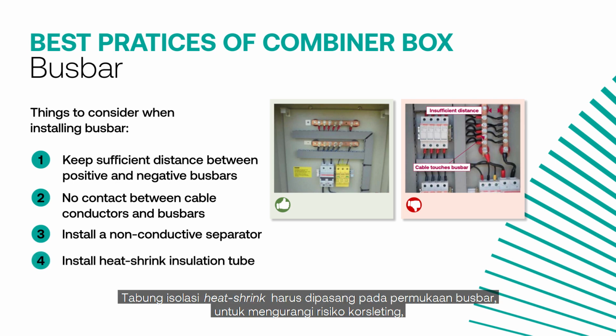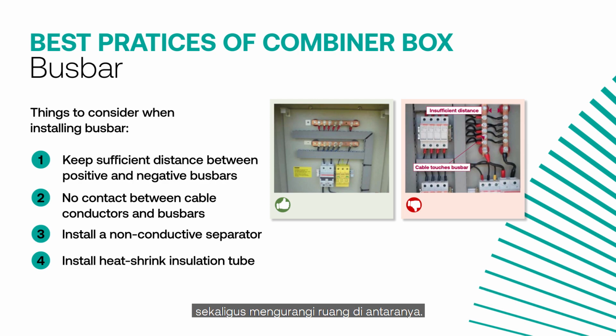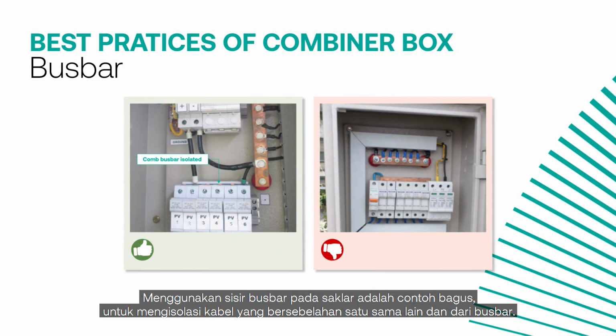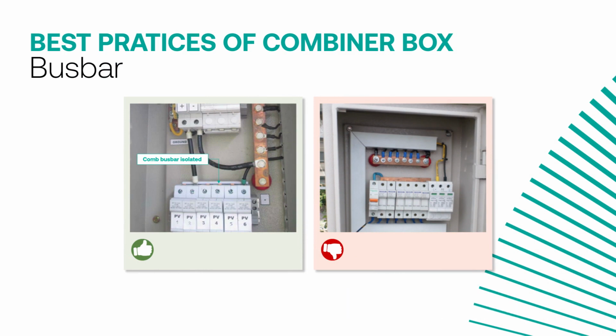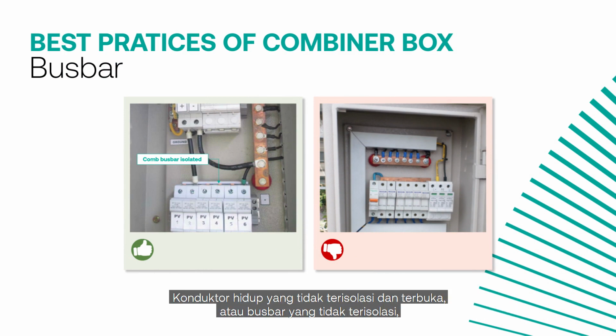A heat shrink insulation tube should be installed on the surface of the busbar to reduce the risk of short circuit as well as reduce the clearance in between. Using a comb busbar on the switch is a good example to isolate neighboring cables from each other and from the busbar. An uninsulated, bare live conductor or uninsulated busbar is a bad example as it is prone to short circuit.